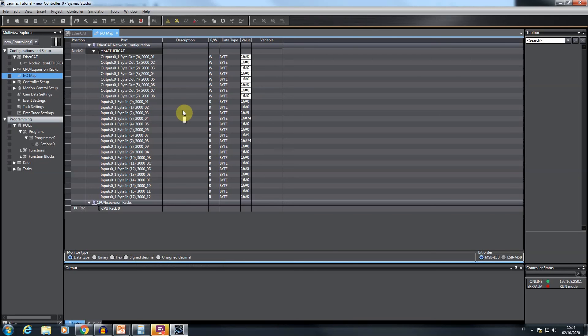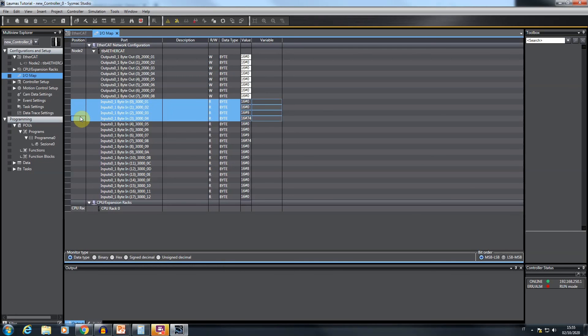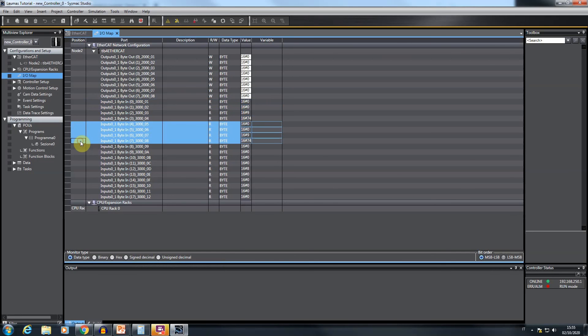With all this information available, after returning to the Sysmac Studio interface, it's quite simple to interpret the values displayed in the IOMAP window. The first 4 bytes in the input section compose the gross weight current value, while the successive 4 bytes compose the net weight current value. At the moment, they are equal because no tare is applied by the instrument.